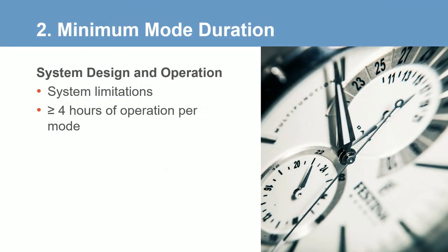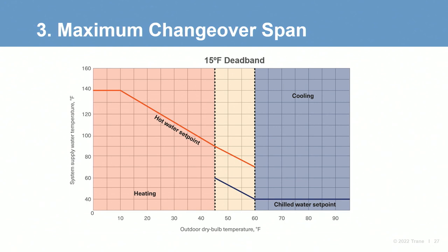Second is that the system controls require at least 4 hours of operation in one mode before changing to the other. This is another limit on preventing the system from switching modes too frequently, thereby cooling or heating fluids that were previously heated or cooled. The last requirement is that the system controls reset the heating and cooling supply temperatures so that they're no further than 30 degrees apart at changeover. This limits the pull-down loads and associated energy consumption after the system is changed over.